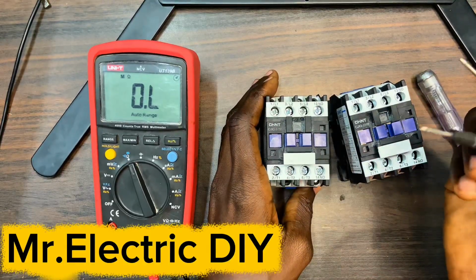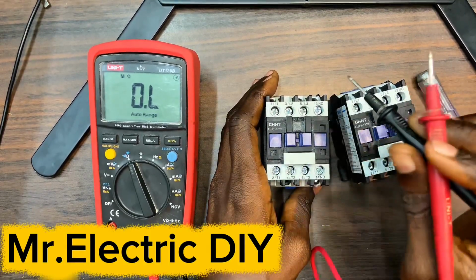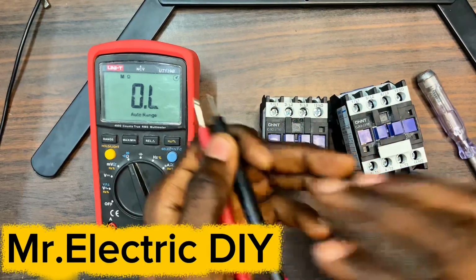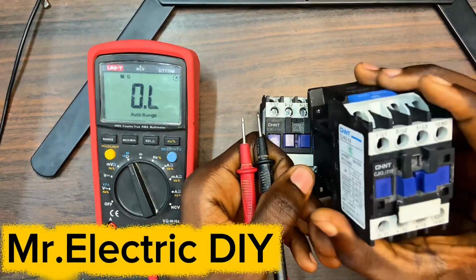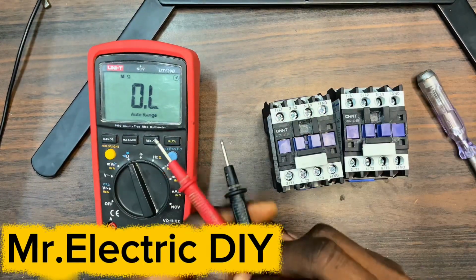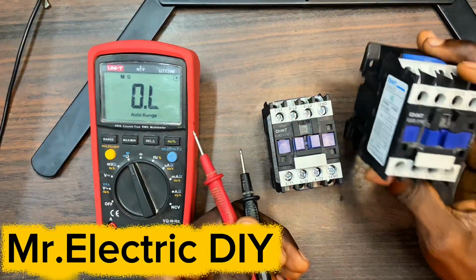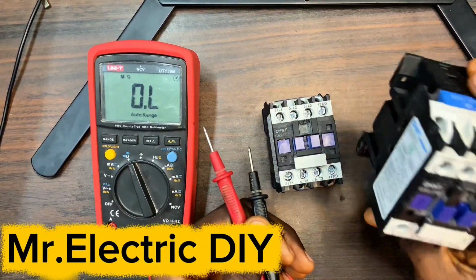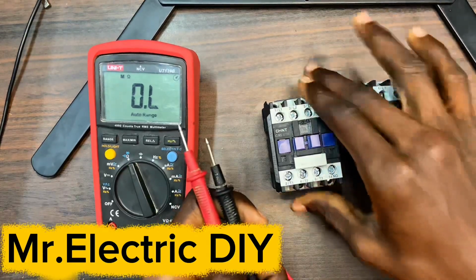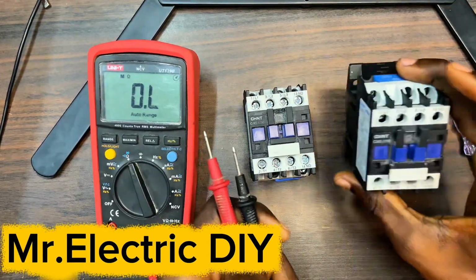Now, if you cannot tell whether the ohmic value here is correct or not, what you have to do is to use a similar contactor and check it. If the readings are right, you're going to have a similar reading on that same type of contactor. So this is the first one that I checked, and this is the second one.